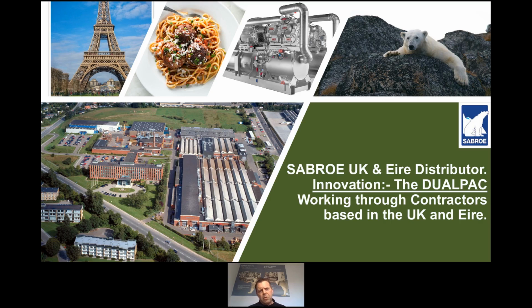The silver unit at the top is our Sabroe DUALPAC, which you can see comprises 2 units. There's a chill side and there's a heat side. It's made through 2 innovations. Firstly, the well-balanced SMC compressor can be stacked on top of the heat exchangers, so that minimizes footprint. The second thing, we have a 3-in-1 heat exchanger inside the condenser part. This reduces the need for multiple separate heat exchangers. So without these, the unit would look like a plate of spaghetti meatballs, which I thought I'd show you just to show you how bad it could be.